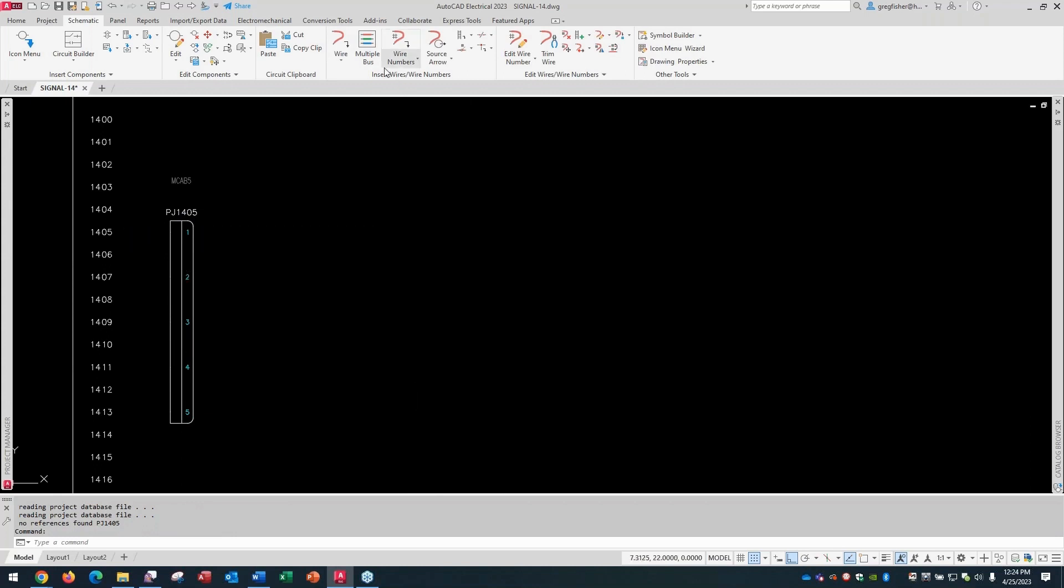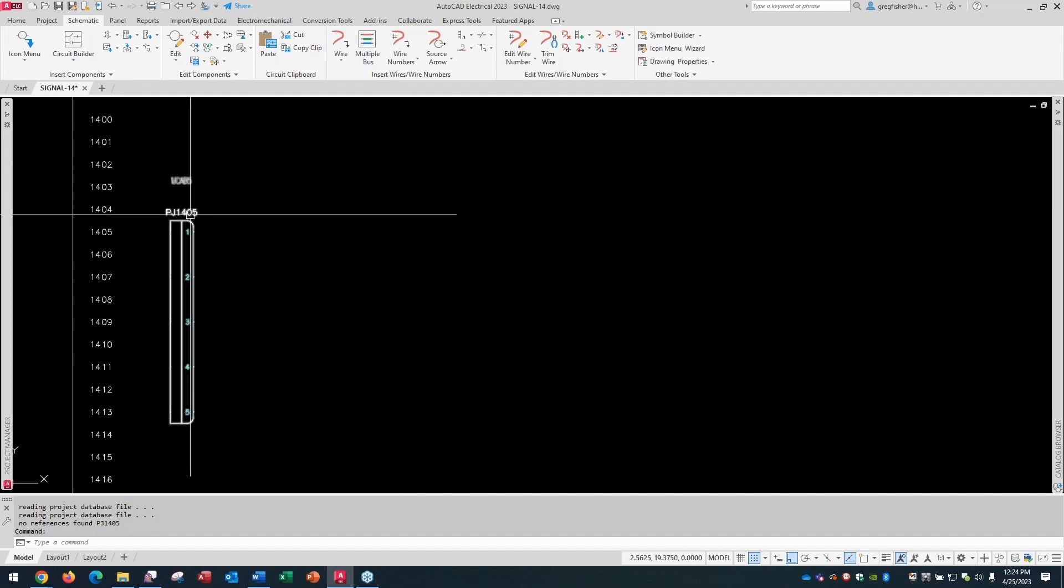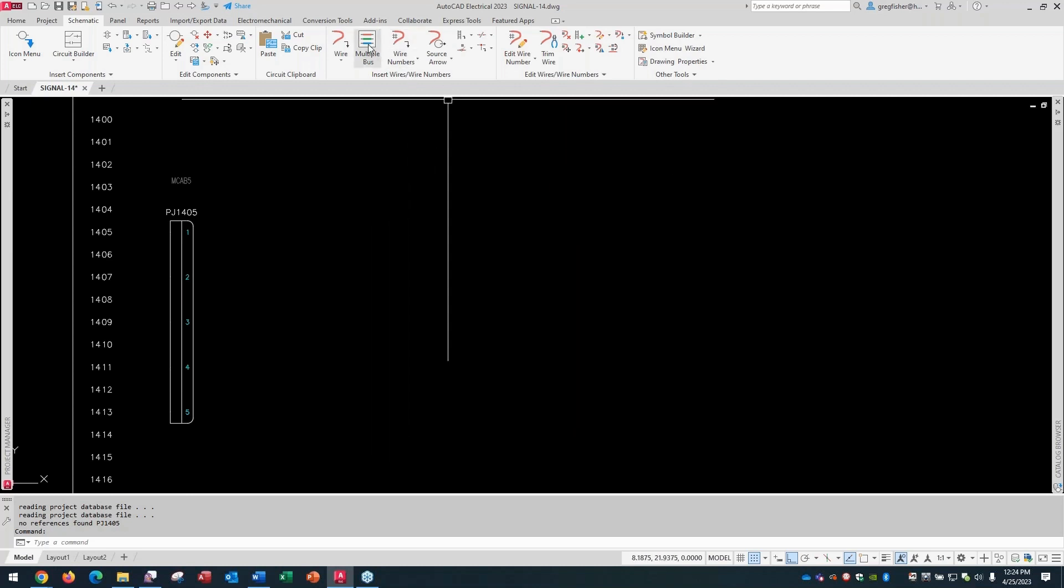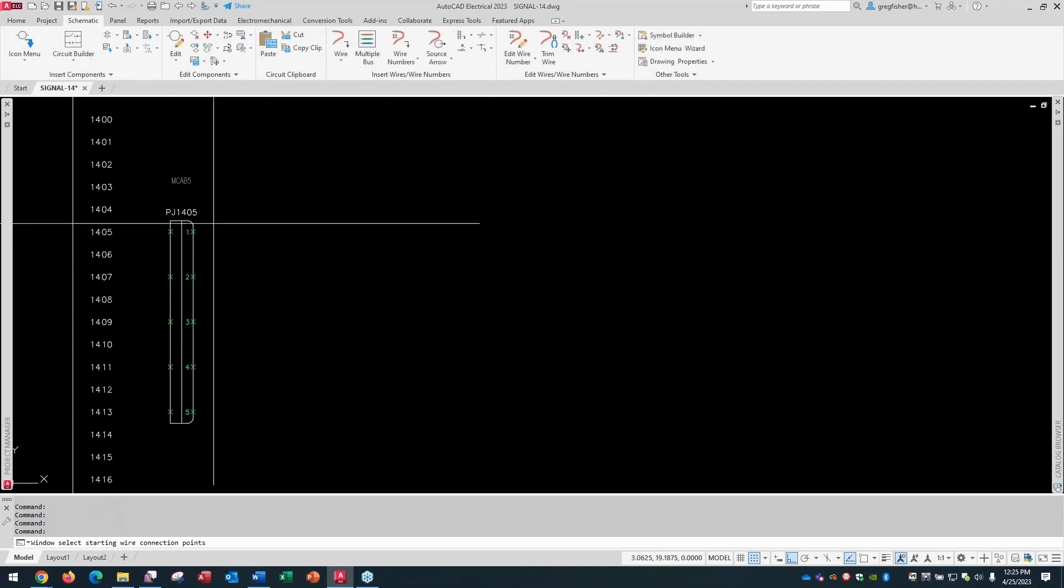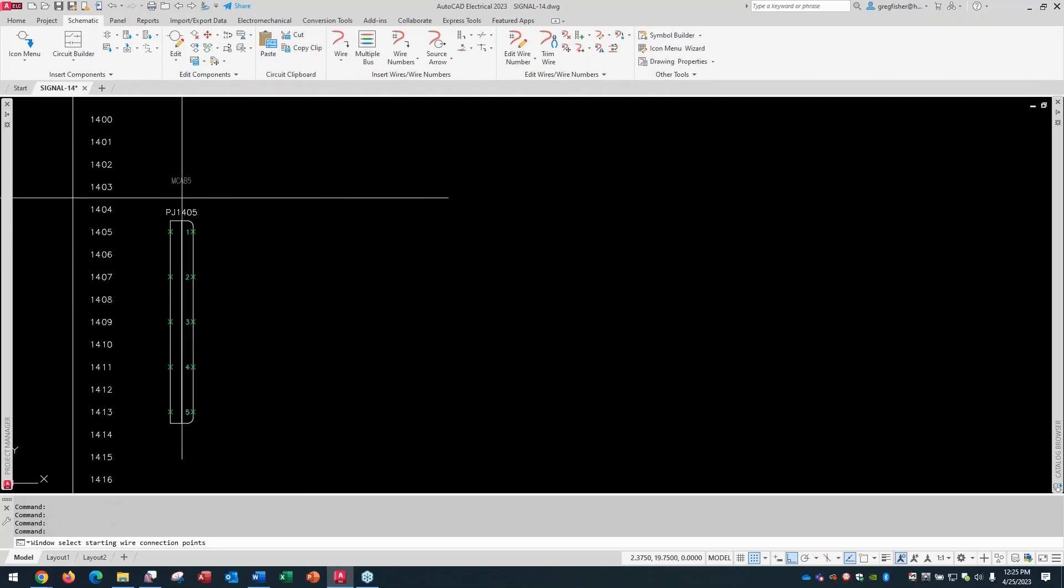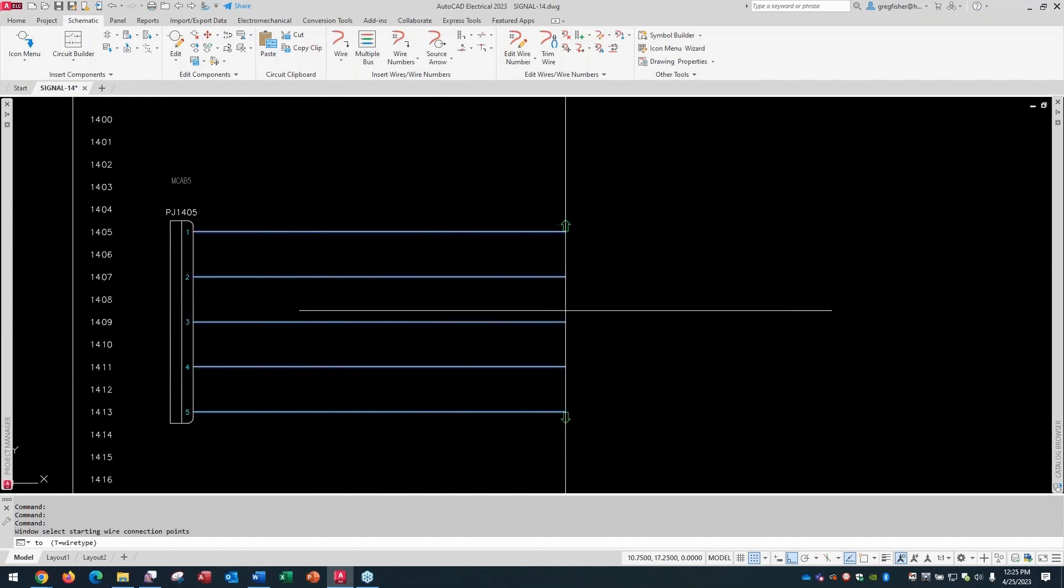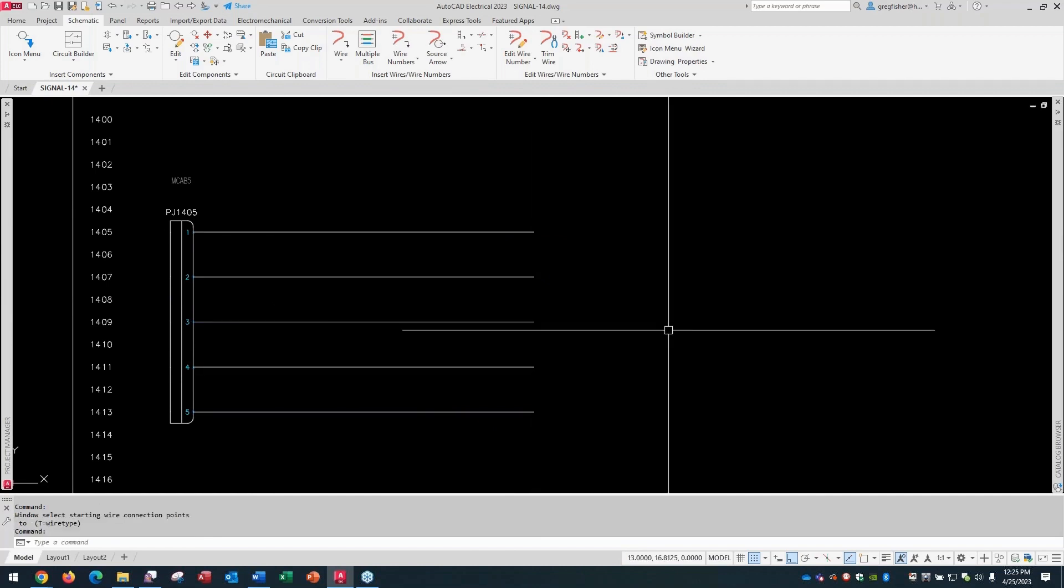And then I'm going to use the multiple bus command. And I'll repeat this in a few minutes, I just happened to insert a connector symbol because it has five connection points, but this could be any symbol. It could be a drive symbol, an HMI symbol. I'm just showing some wires coming off of one symbol and going to another is what's going to happen at the end of the day here. So I'm going to go to my multiple bus command. And I'm going to start it at a component with multiple wires. And then I'm going to wrap a window around my connection points and just draw some wires. I'm going to put it randomly out to about here, giving myself a lot of space.